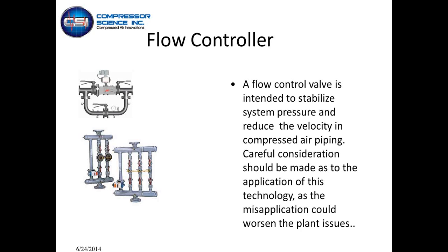What the flow control valve does is limit the velocity of compressed air through the entire piping system by maintaining a steady pressure. Because with the pressure swings that we see in compressed air systems without proper storage, of 20 or 30 PSI, we've got 15, 20, 30 pounds of swing in the pressure in the system, which is causing operating problems with process, because that process may not be able to work at 80 PSI, and at the bottom end of the swing, it's just happened to catch that part of the production that needs 100 that's now got 80. A flow control valve's purpose is to maintain a steady velocity and pressure throughout the piping system and allow you to deal with certain events out of storage or stabilize the system pressure by applying enough storage in it, similar to a lake in a dam or a capacitor and a resistor.